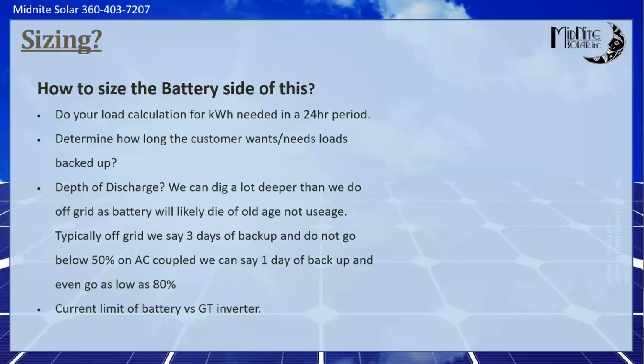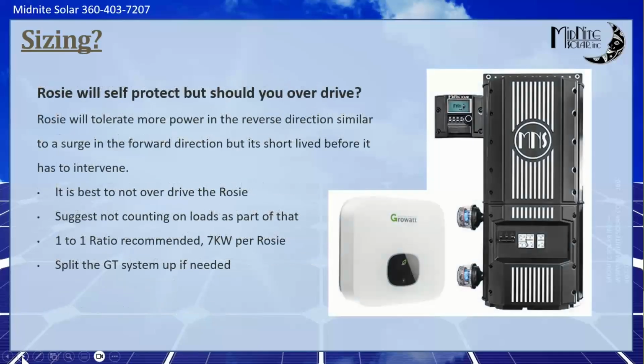Also look at the inverter's recommendations. Some inverters have a pretty stiff recommendation for amp hours or kilowatt hours of battery per kilowatt of inverter. The Rosie is a lot less picky than some. You can run a Rosie on a 5 kilowatt hour server rack battery. I would personally suggest 2 as a minimum. The all-in-one, I think, is about in that same ballpark, but some other competitors' inverters do have some requirements on minimum battery capacity. So do be aware of that one as well if you're not using a Midnite inverter. But you should be using a Midnite inverter.